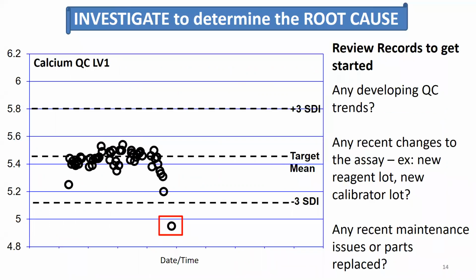Once the assay or instrument is taken out of service, troubleshooting can begin. We can examine the Levey-Jennings charts for the calcium level 1 QC to see if there are any shifts or trends that are developing, and if we can pinpoint the actual date and time the problem started. We can check the laboratory records to see if any new reagent lots or new calibrator lots were first implemented when the problem started. We can check the status of the maintenance for the instrument. So were there any recent maintenance issues or instrument parts replaced? So these types of investigations can provide clues about the root cause of the problem.